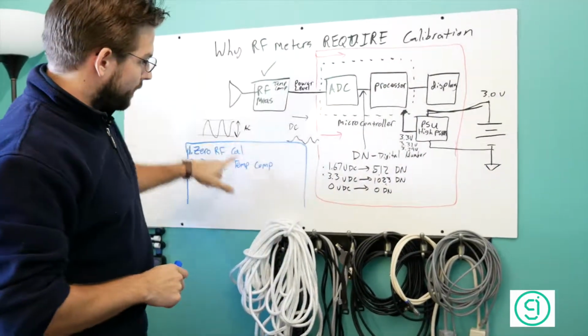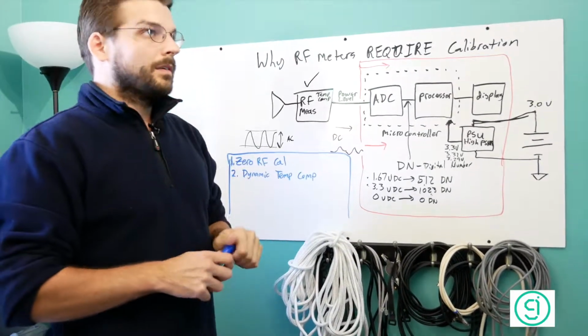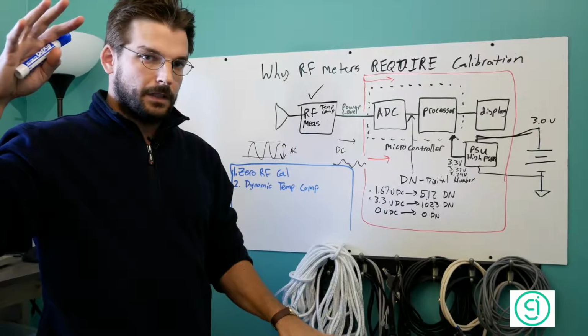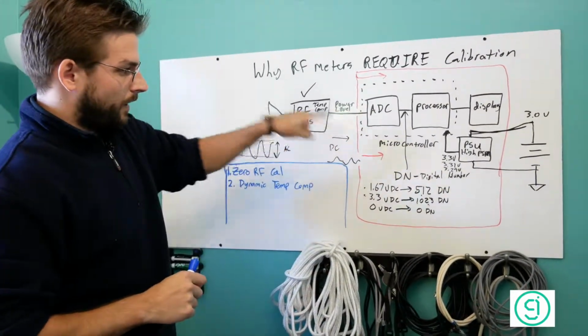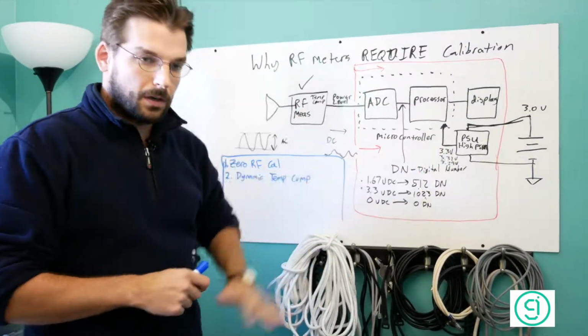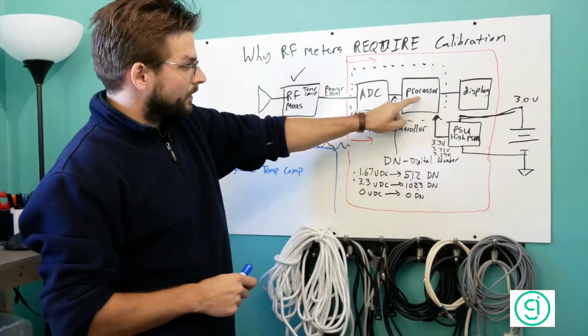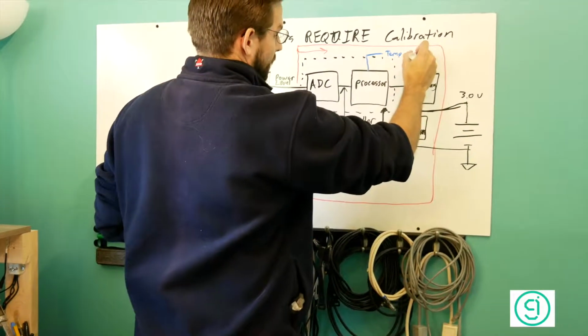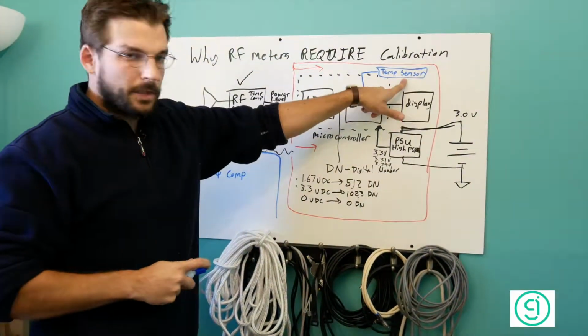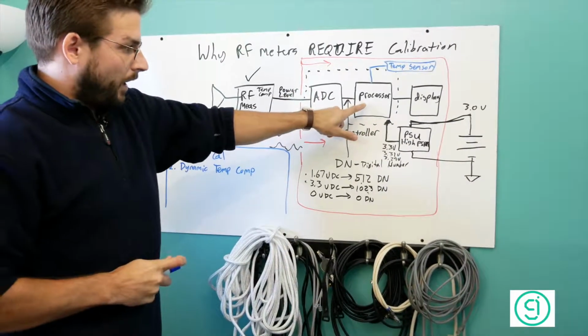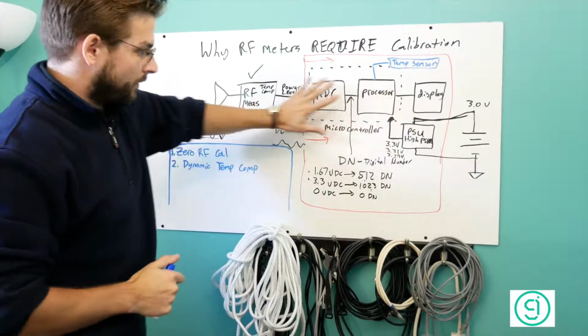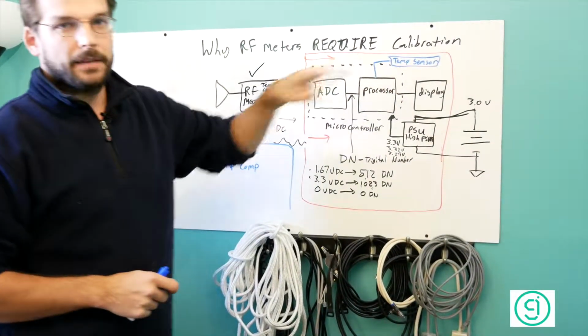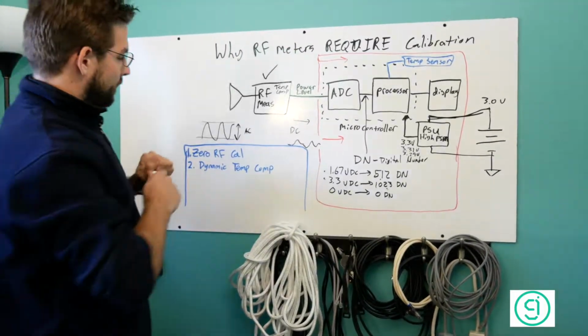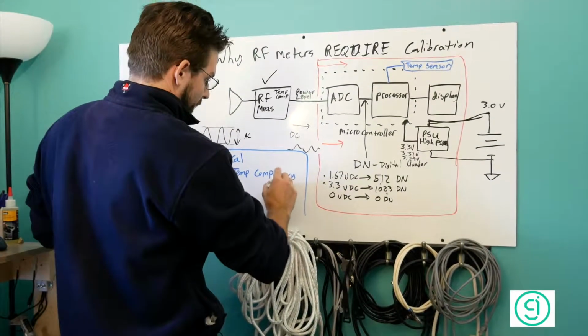So what we've done is we've taken the entire device from about negative 15 degrees Celsius to about positive 50 degrees Celsius, and we've figured out what the characteristic offset curve is. So we figured out how the measurement changes across that range of temperatures. And then inside the processor, we have a temp sensor, and every 3 seconds we measure the ambient temperature of the device, and we run our correction algorithm to adjust the measurement offset to what the correct value should be at that temperature. So, dynamic temp comp every 3 seconds.